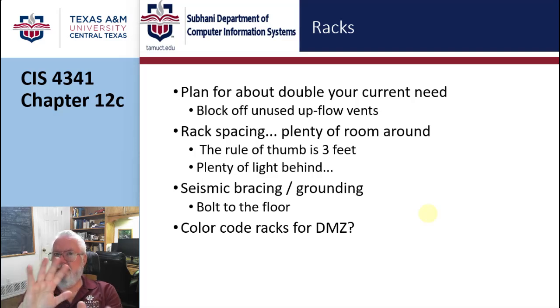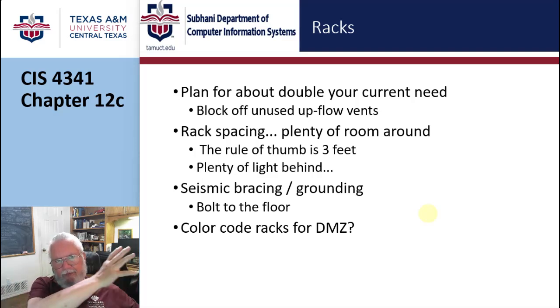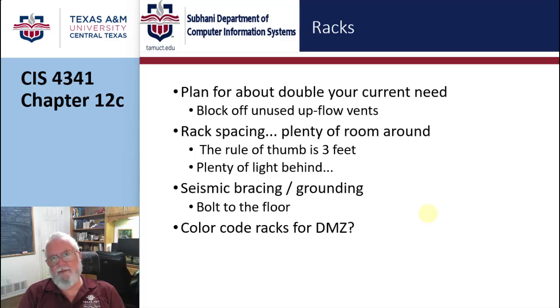Like, no. We would even tape off with tape on the floor where the next rack is going to go. So we could see there's 3 racks here, but there's 3 spots over here that are designed for future racks. Anyway, lots of room and lots of space around the rack. The rule of thumb is 3 feet. Make sure you have plenty of lighting, particularly in the back.